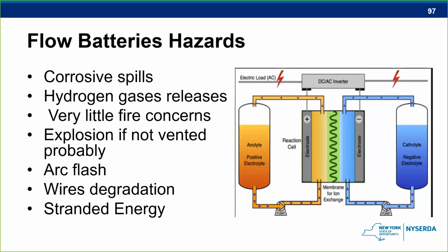But our biggest concern with these things are the corrosives that are inside those vessels that you see, one marked in orange, the other one marked in blue, and they pump. There's a pumping action that takes place, and as a result of that pumping action, energy is created. But once you shut down that pumping action, then we can dissipate that energy, and that's the one good thing about flow batteries. We thought in New York City that these things would make a big splash, no pun intended, but really we didn't see too many of them.